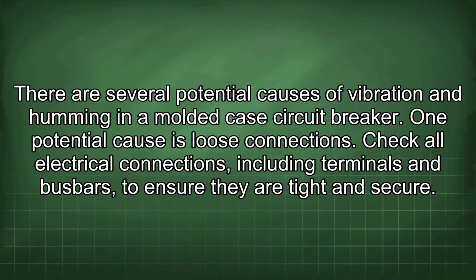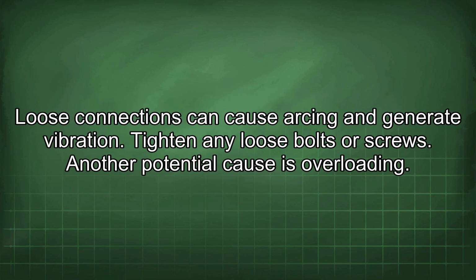There are several potential causes of vibration and humming in a molded case circuit breaker. One potential cause is loose connections. Check all electrical connections, including terminals and busbars, to ensure they are tight and secure. Loose connections can cause arcing and generate vibration. Tighten any loose bolts or screws.